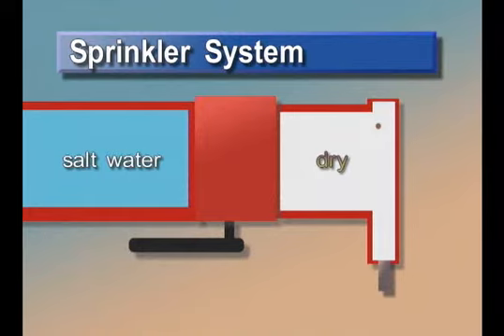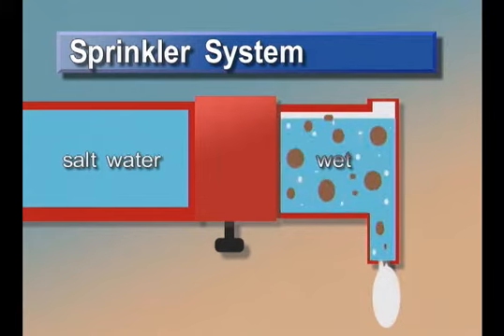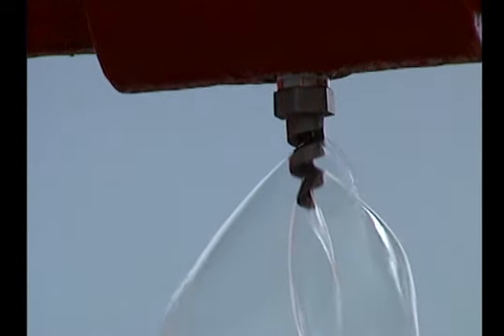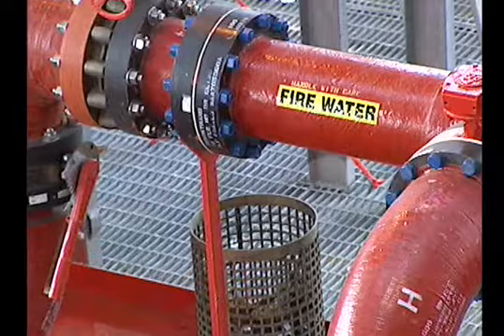Typically, a sprinkler system remains dry with saltwater contained behind deluge flood valves until activated. Conventional carbon steel sprinkler piping may sit unprotected in a corrosive atmosphere for years before it is needed. While the OD of this pipe is maintained by cleaning and painting over its service life, internal corrosion will progress unobserved and untreated. When this sprinkler system is activated, the incoming rush of water will flush rust and corrosion forward to the sprinkler head, where scale will quickly block the flow of water and render the sprinkler system useless.